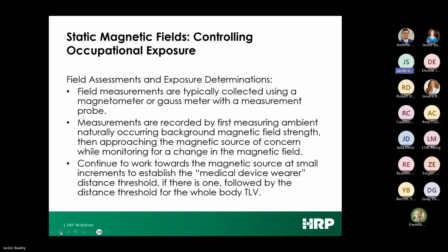It's a little unique for magnets because a lot of these meters come in specific ranges, and it's important to use the right equipment for the right type of magnetic field, whether static or alternating, and to make sure the range of the probe matches the field you're looking for. Sometimes it's handy to have a couple of different probes to be sure you're capturing all the magnetic field in the device, similar to using an ohm meter for electrical work.